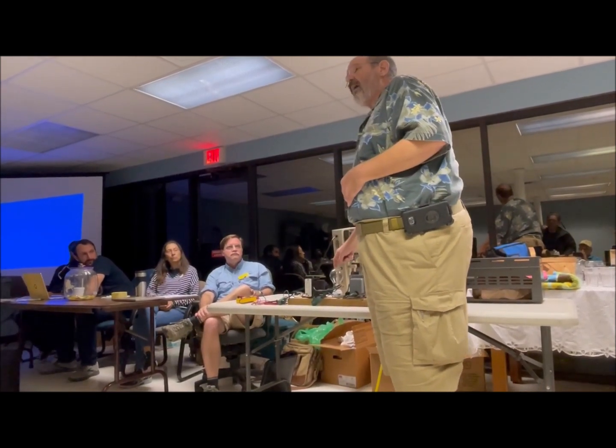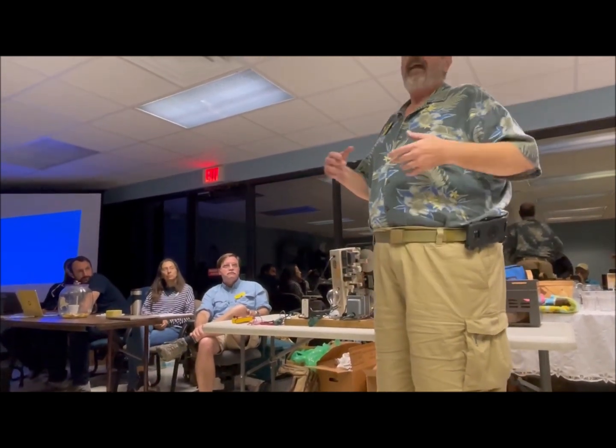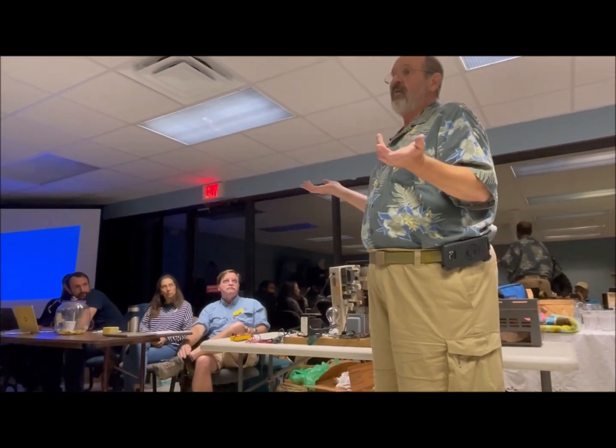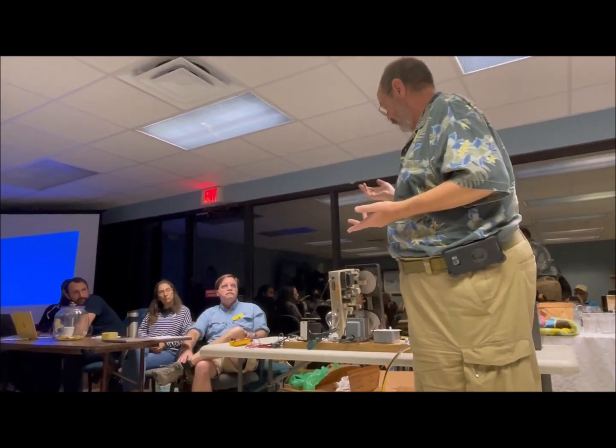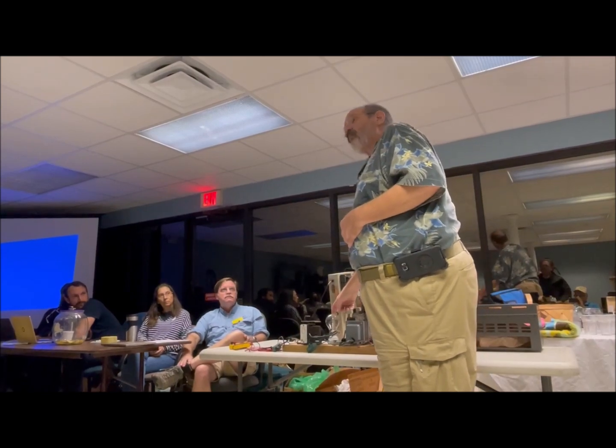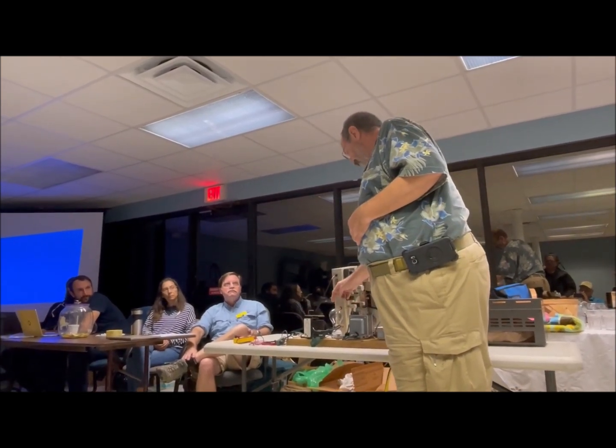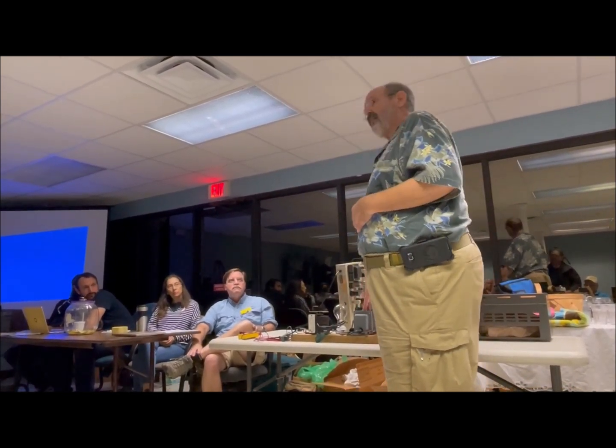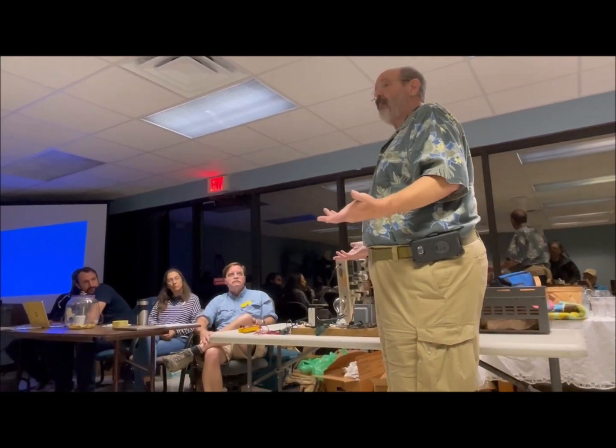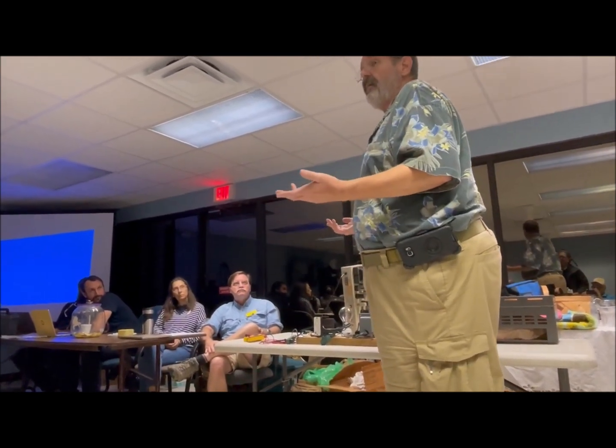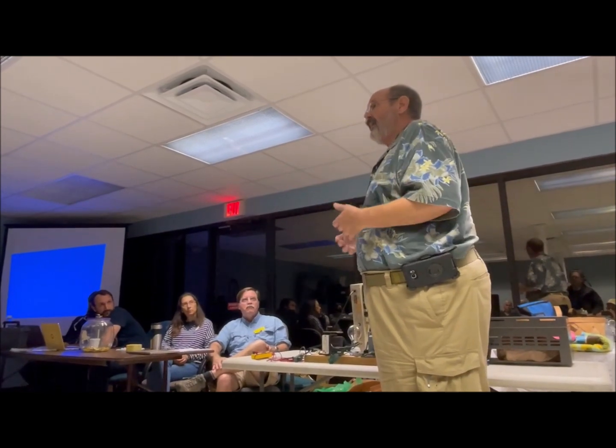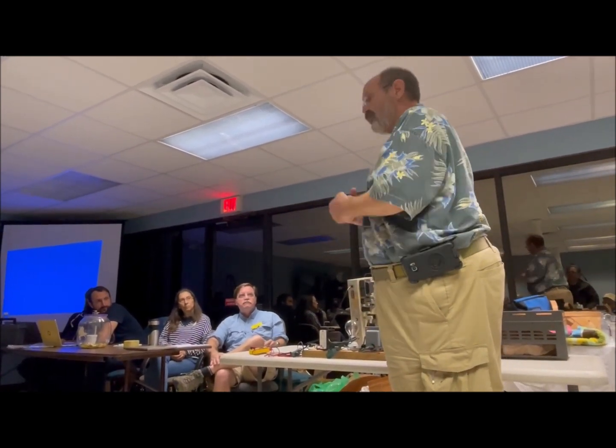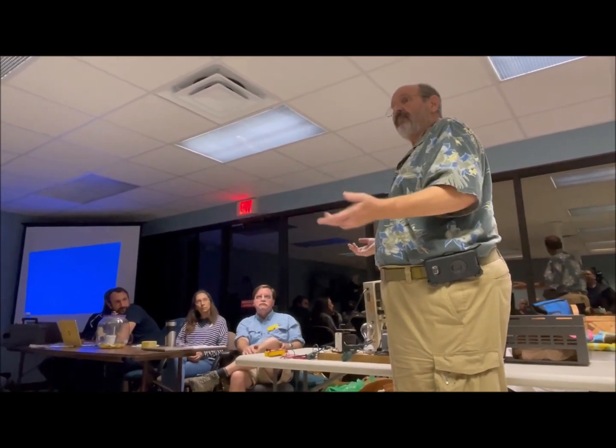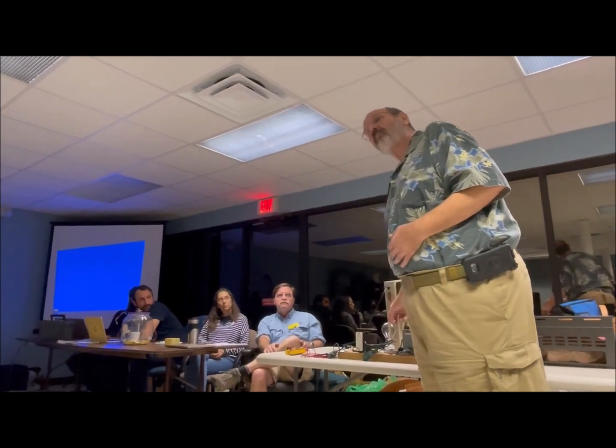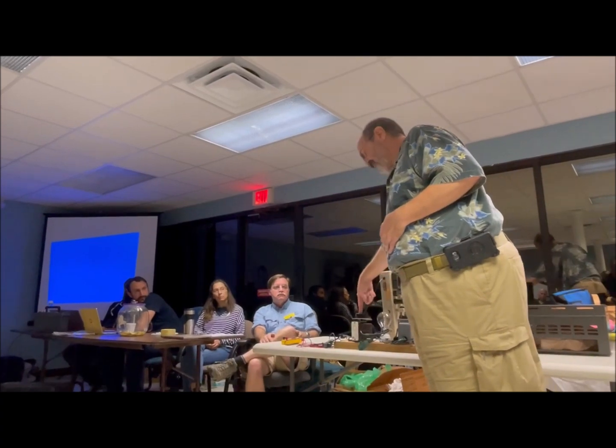The lamp at 200 watts—if you divide 200 by 125, since our house voltage is typically 120, you get about 1.6 amps. So if I were to short the lamp across the isolation transformer and power it up, the most I'd get is a bright lamp, and it limits the current. If I short it out, I don't blow things up. You can tell how much current's going through by how bright it is—it's like a fuse in series. Then I can adjust the voltage from the variac.